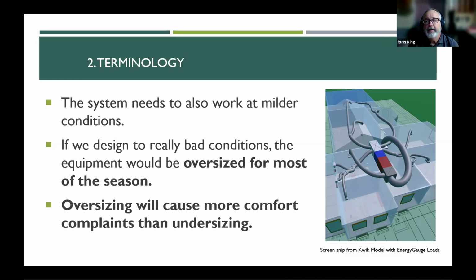In fact, the industry standard for sizing equipment is called Manual S, okay? ACCA Manual S, and it says that it is perfectly acceptable to size your equipment for up to 10% less than the load calc. It is perfectly acceptable to size your equipment for 10% less. 90% of your load calc is an acceptable sizing criteria. Okay, so just be aware of that. And then they have maximum oversizing limits as well, okay, depending on the type.